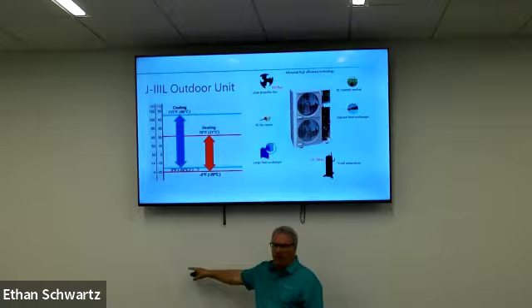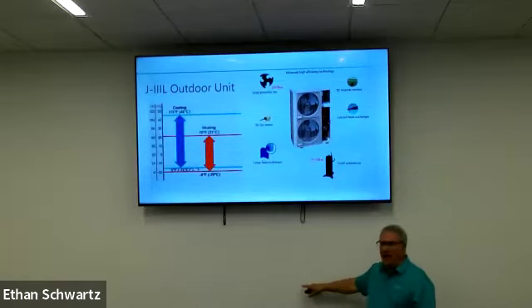And remember when I told you about the outdoor unit having an electronic expansion valve for the indoor unit. When that liquid line runs outside of the building, which it most likely will, even for any amount of length, and you're in that -5, -10 outdoor temperature, we are going to subcool. That refrigerant in that liquid line will be subcooled.